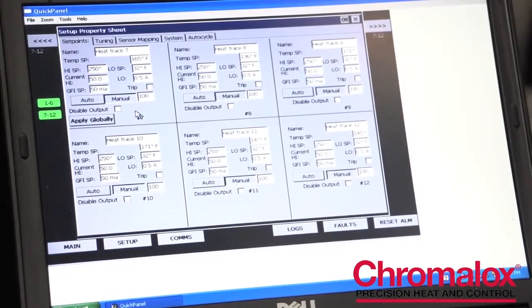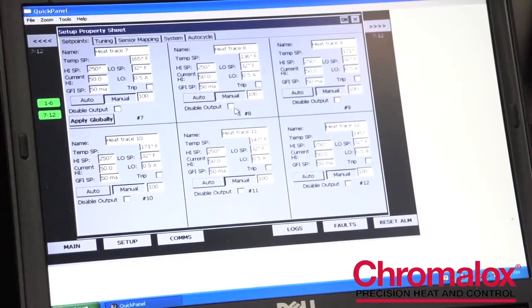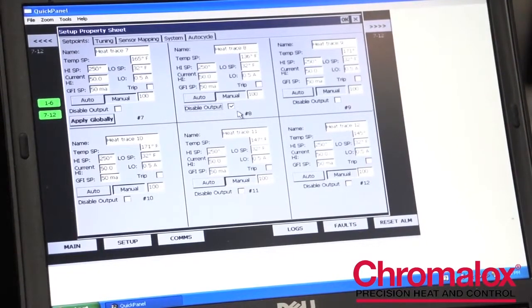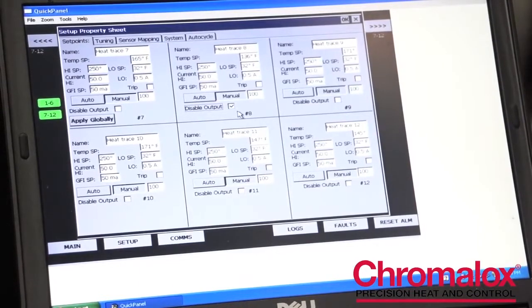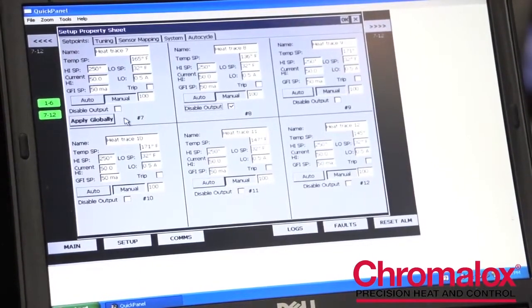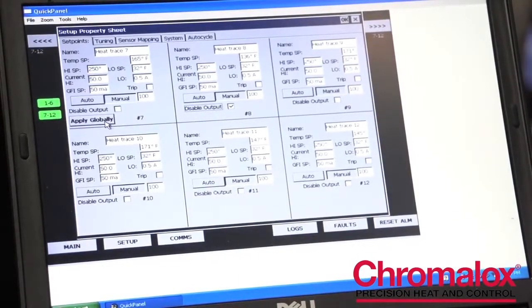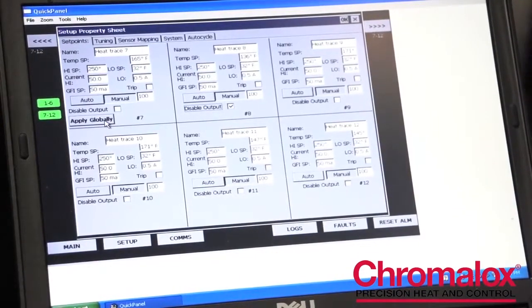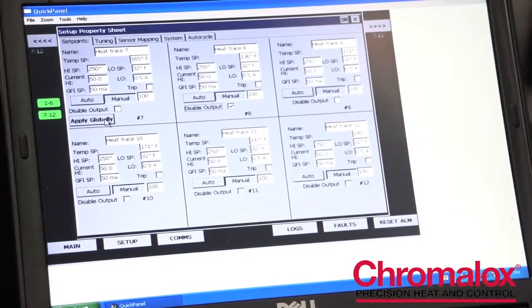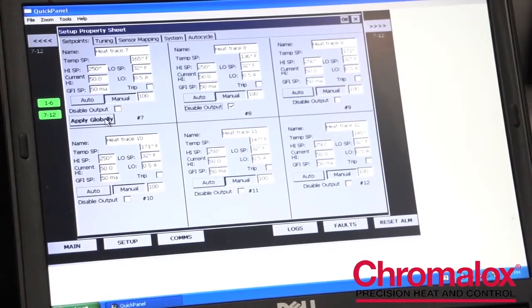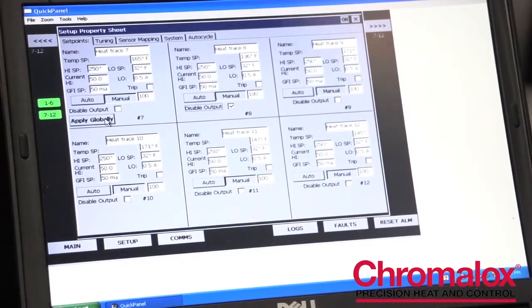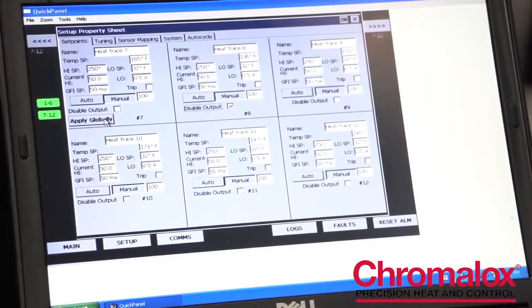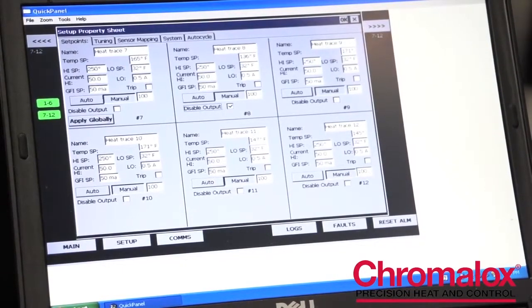You can also disable any individual circuit by simply selecting disable that circuit and that circuit can remain off if you need to do service on that line. You can also set up one circuit and that circuit can be the guide for all of the rest of the circuits by hitting apply globally. So all the parameters that were set in that one circuit will be applied to all of the circuits. It saves you a tremendous amount of time.